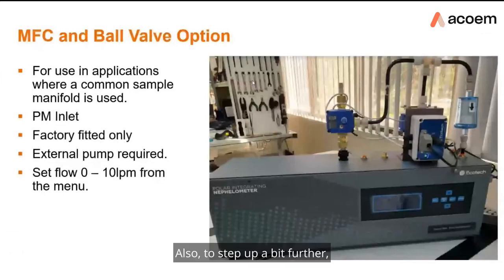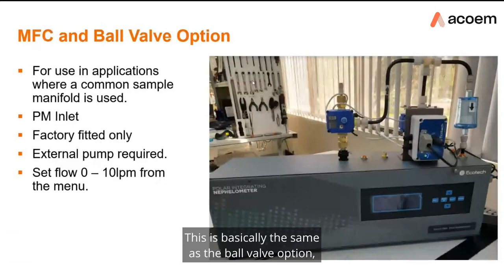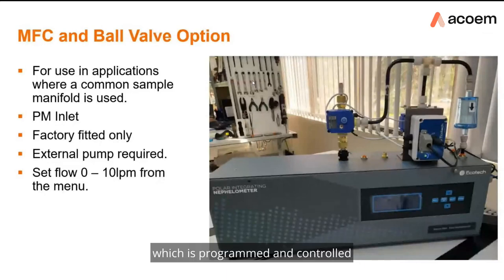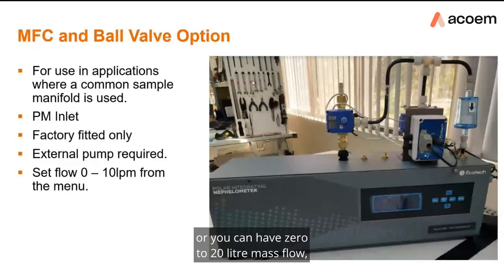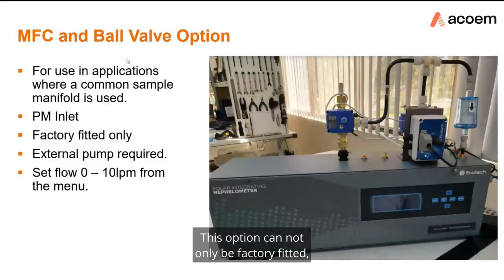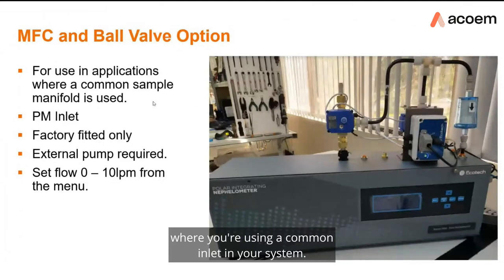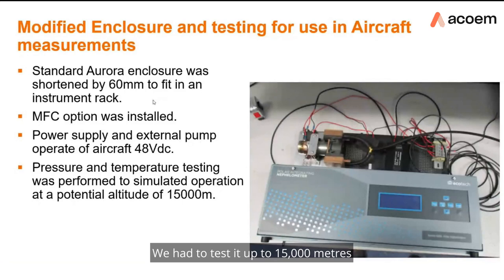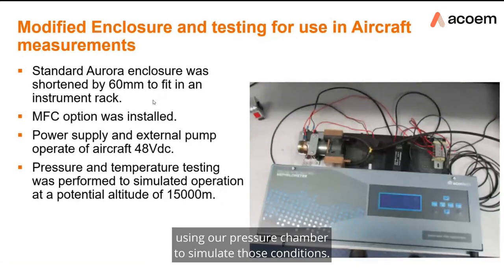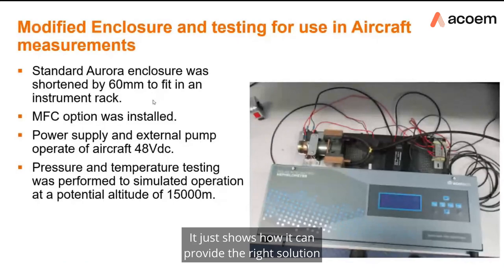A further step up is the MFC and ball valve option, which is similar to the ball valve option but includes an internally installed mass flow controller programmed and controlled by the Aurora nephelometer itself through the front menu. You can set the flow between 0 and 10 liters per minute, or 0 to 20 liters per minute if desired. This option is factory-fitted only and is ideal for matching flows with other instruments on a common inlet. An example was an Aurora 4000 designed to fit in an aircraft fuselage, tested in a pressure chamber to simulate 15,000-meter altitude conditions.